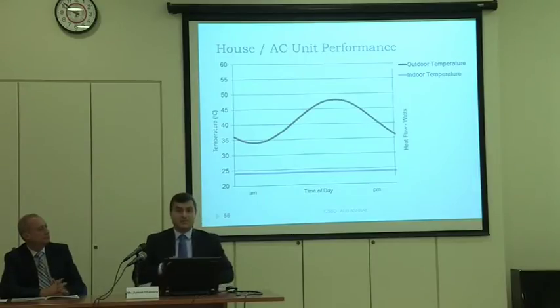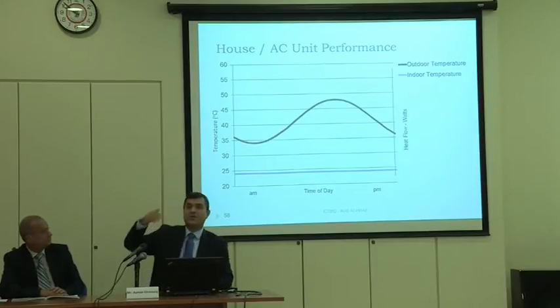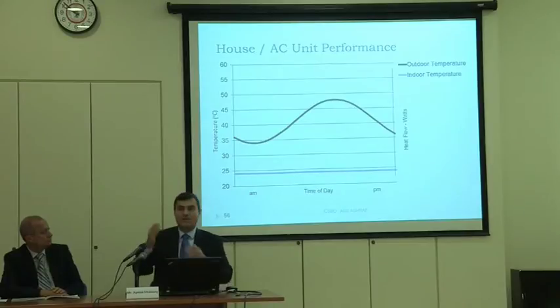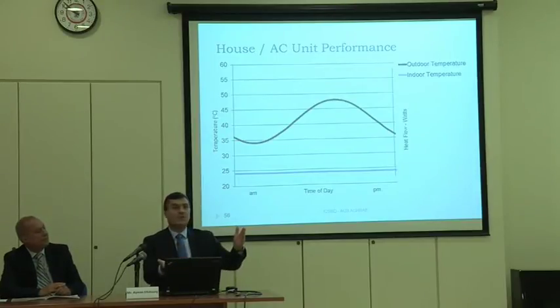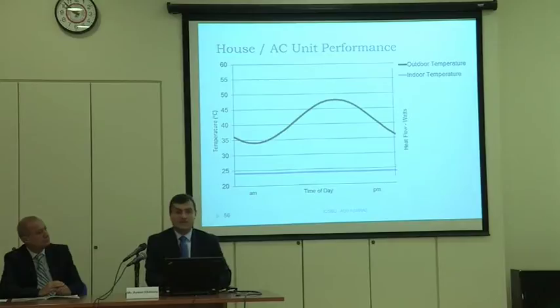Now again, I want to make sure that you understand why 46 in there. Because we believe, even though the temperature can go high in the day to 50, 52, the design is 46, because there is a time lag between the temperature outside and the high cooling load inside the house, due to the mass structure of the house. For example, we want to maintain a temperature of 24 inside, we want to keep the room cool. The outside temperature goes high. This is one typical day, for example, from 35 all the way up to 46 or 48 degrees C, and then it goes down during one day in July, for example, in high temperature.